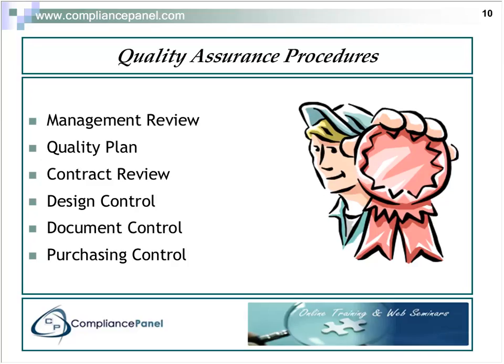Your design control procedures, again, these are all documents and operations which I'm sure anyone in the device industry has to have in place anyway. But the key is that you're following these and that your design process output is documented properly, that you've got a proper development plan, a proper design review procedure, and that you're following these. And for things like third-party software that is either being used as part of production or as part of your product, you need the proper methodology for the control of the designs and the control of the documentation that's associated with that.